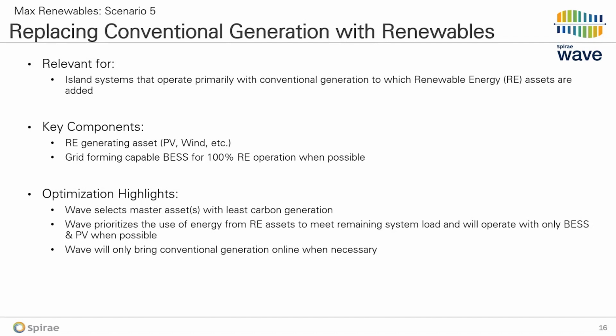So what we're going to be doing there is reintroducing those batteries, making them available to the system to control. And then once the system recognizes they're available and are sufficiently charged for our purposes, then it will use those as its preferred resource and switch over to use the batteries and back off and turn off the conventional generation. So let's take a look at what we can see with the wave controller for this scenario.